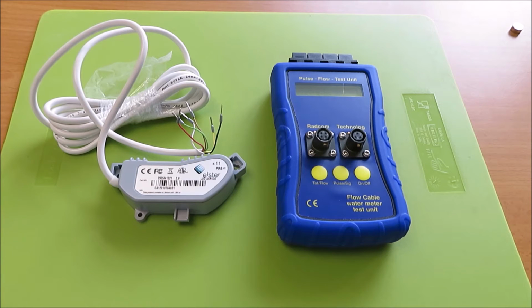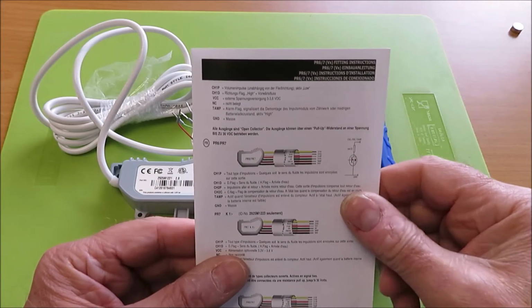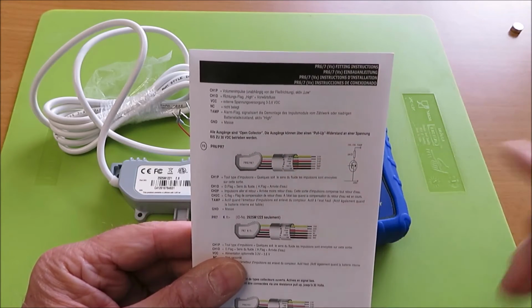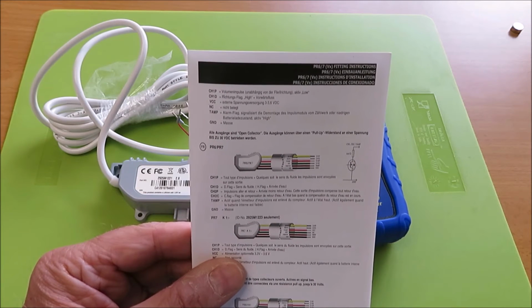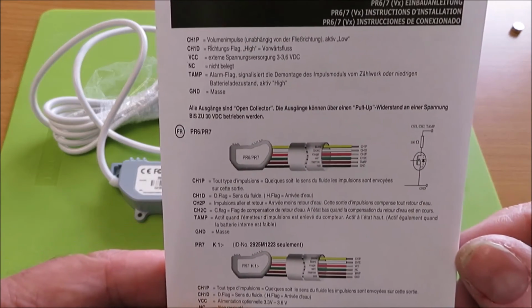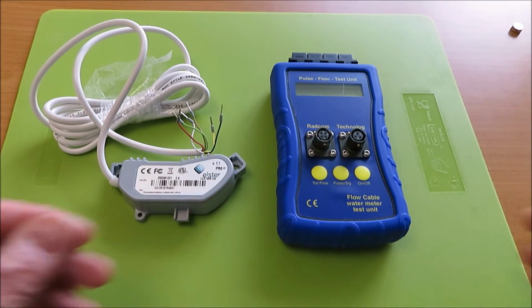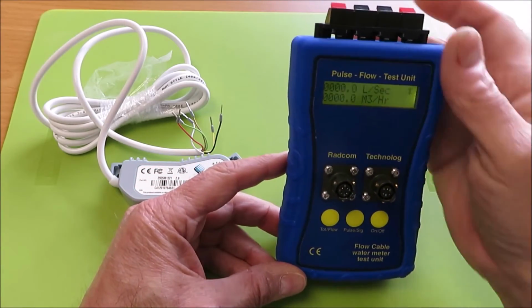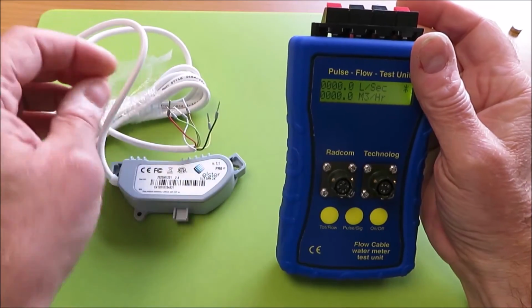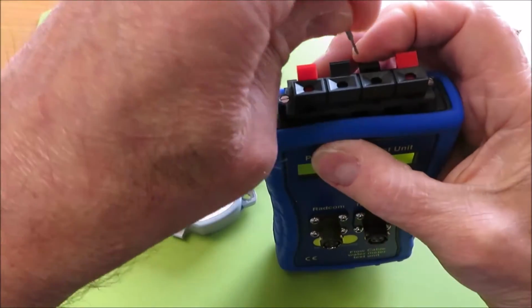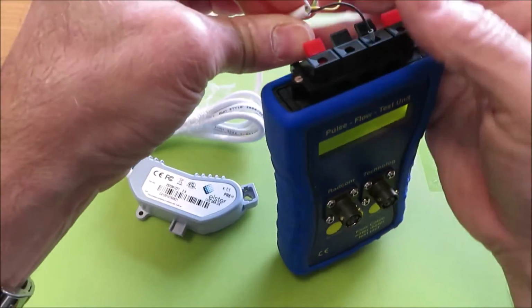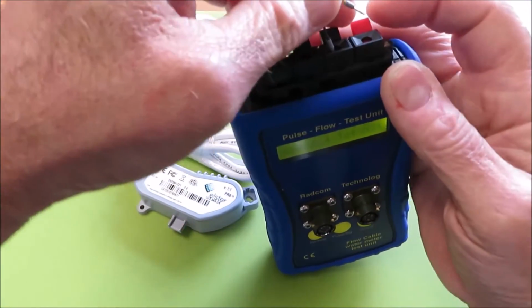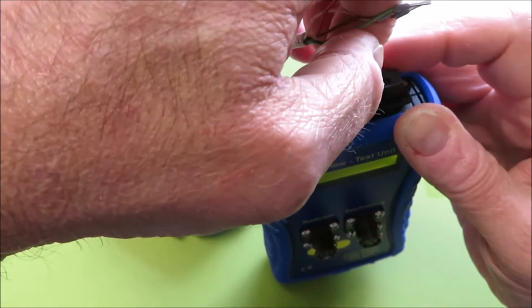Now I'll demonstrate the PR6. So what I'll demonstrate next is the PR6 flow sensor, and if we look at the instruction manual, looking at the top here for the UK, you'll see that actually the channel 1 or primary is the yellow wire and the ground is the black wire. So what we'll do is, as we did with the previous pulse test unit, we will put the black wire into the black connector and the yellow wire, which was the channel 1 primary on the PR6, into the red.